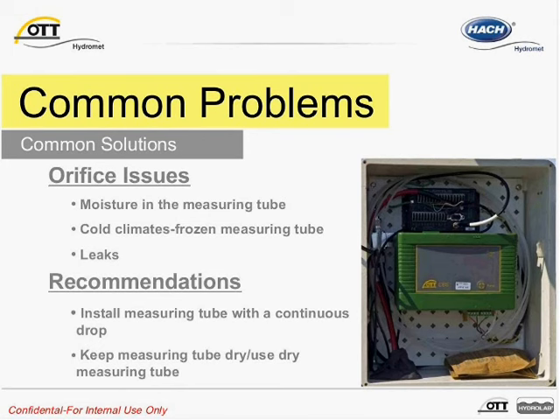So if water does freeze in the tube, it would prevent the CBS from being able to push out air through the bubble chamber, and therefore would result in an overload pressure, and you would receive a status message.